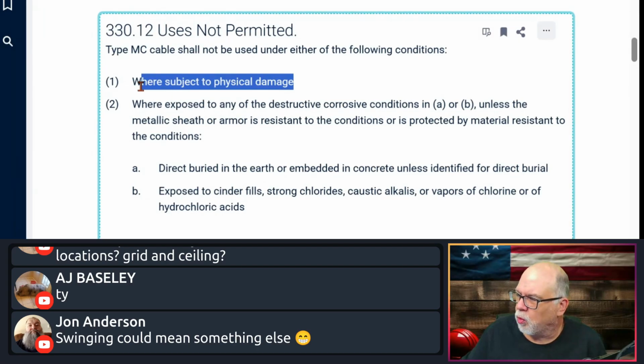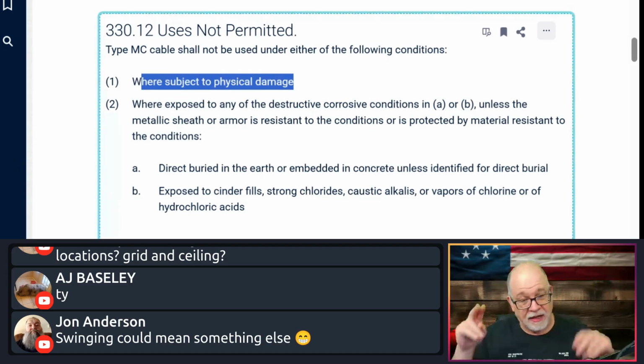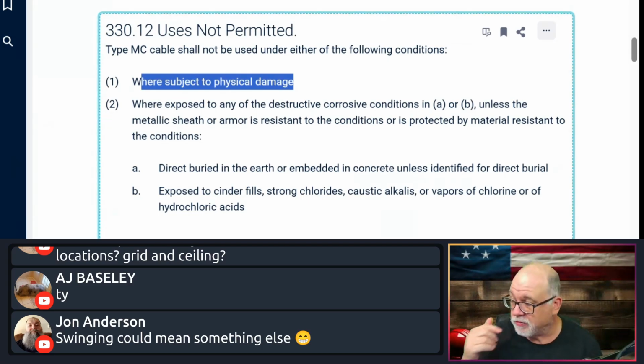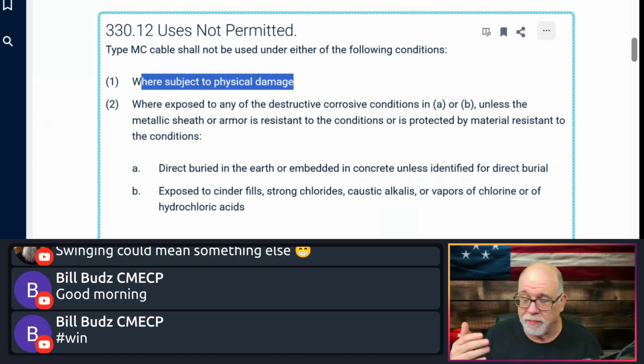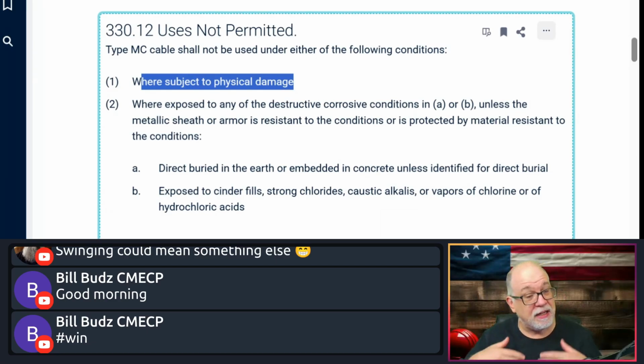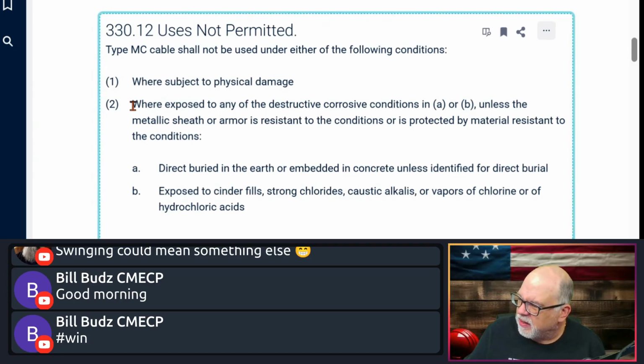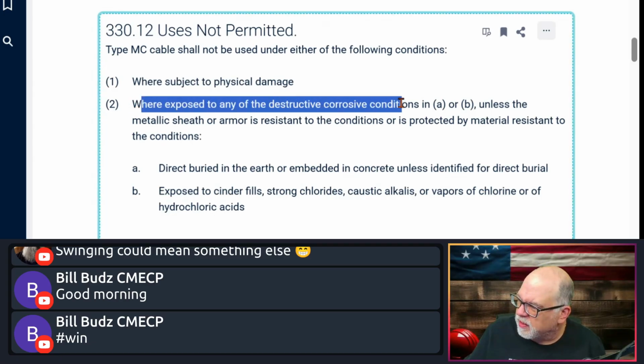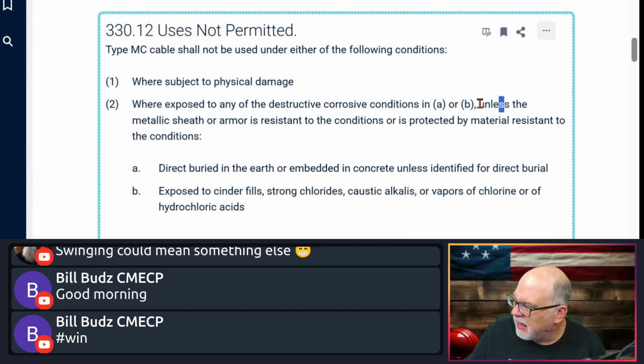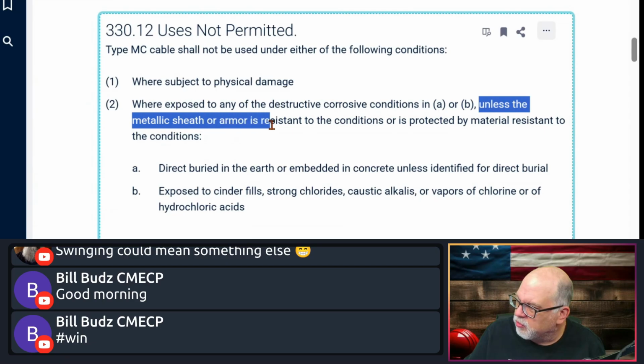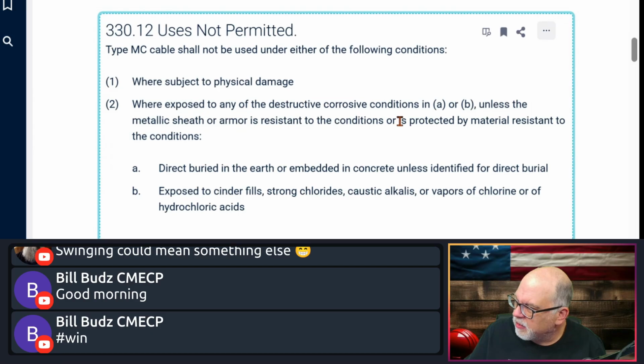All right, anyway. So here's uses not permitted. First, where we're subject to physical damage. Now, this might be an example where you sleeve it in a raceway in an area that is subject to physical damage, okay? So you might sleeve it in EMT or do something like that. That's the idea, and that's why it is okay to put it in a raceway. Number 2, it says where exposed to destructive corrosive conditions in (a) or (b), unless the metallic sheathing or armor is resistant to the conditions or is protected by material resistant to the condition.